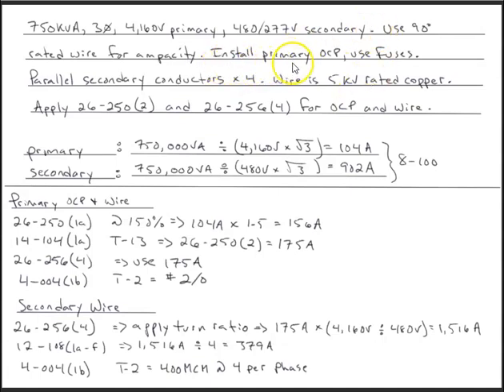So here we're going to install a primary overcurrent protection. We're going to use fuses. We're going to parallel the secondary conductors by 4. The wire itself is 5 kV rated copper. So 5 kV meaning the insulation rating. But the voltage being applied is still 4160. We're going to apply 26250 subrule 2 and 26256 subrule 4 for the overcurrent protection in the wire.